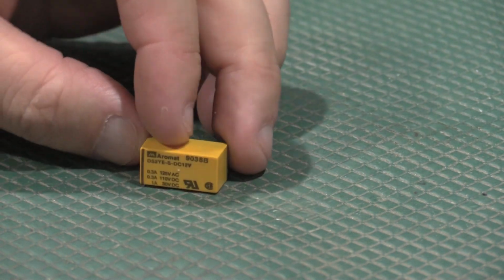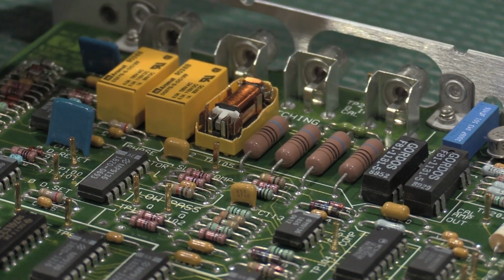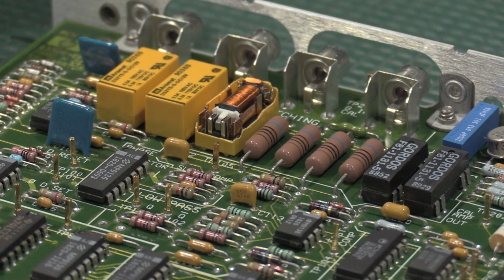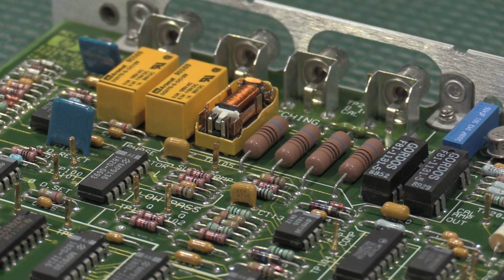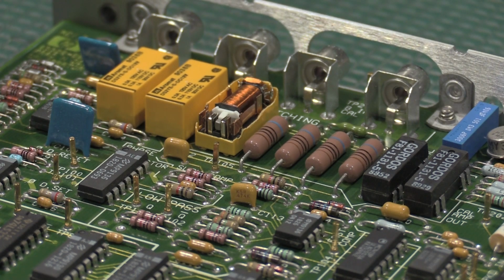And we'll get some in and see if we don't make some improvements. I've pulled the cover off this relay, which is usually a bad idea to leave in circuit, but I did get the contacts cleaned up, and got the contact resistance back down to 0.1 ohm, a little over the 0.09 it was before. So we're going to put this back in and see if our DC offset problem goes away. If it does, we'll know for sure it's this K5 relay and get some parts on order. This will let us validate the troubleshooting logic. This unit's going to stay in the lab under my care if it gets repaired, so it won't be a problem to crack it open and throw a new relay in once parts come in. Let me get this put back in and we'll see what happens.